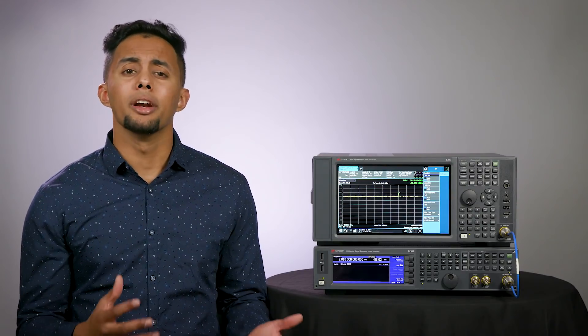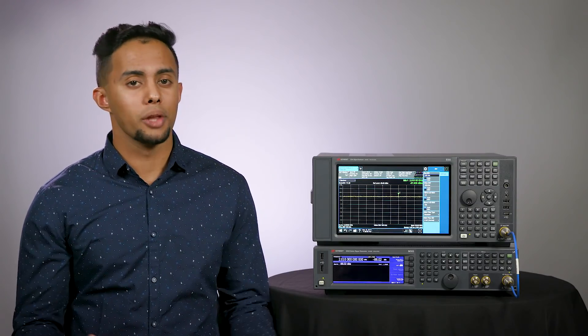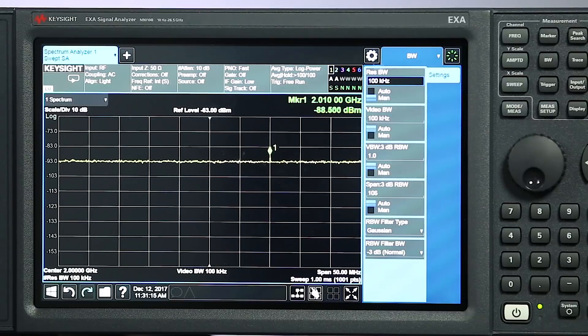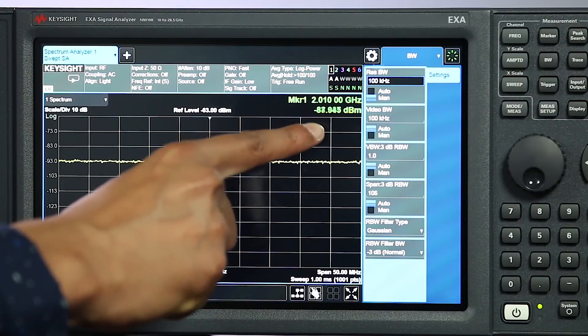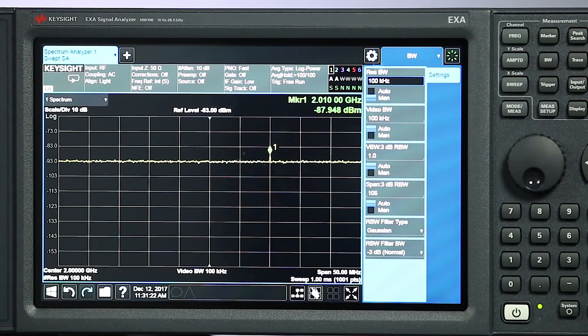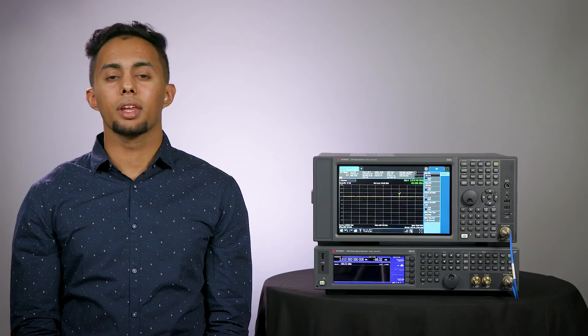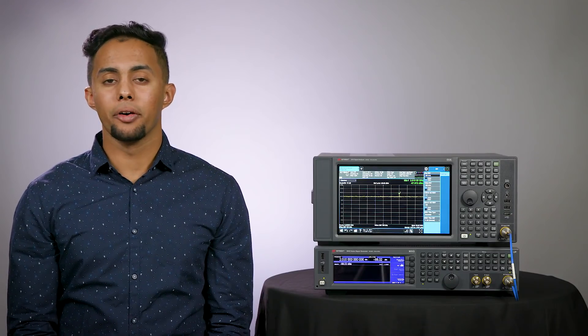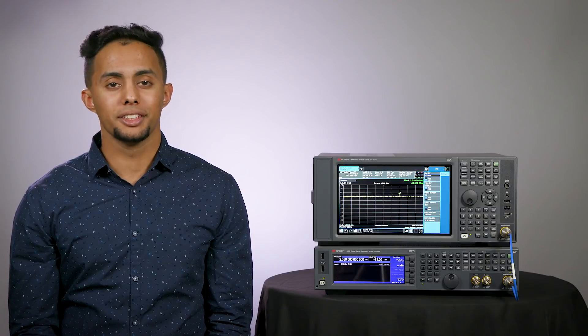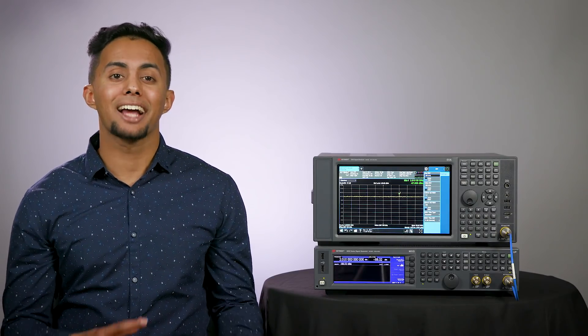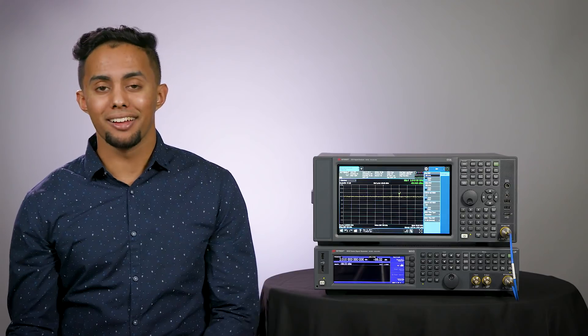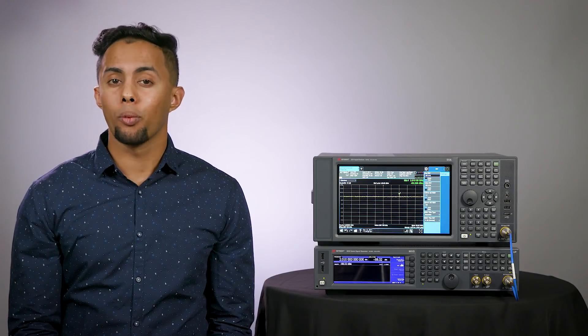Let's take a look. Let's assume we're looking for a low-level signal such as a low-level spur. On this screen we have an apparent minus 88 dBm signal at a frequency of 2.01 gigahertz, and we are sweeping with a resolution bandwidth of 100 kilohertz. We just barely see the spur here rising a bit above the noise floor, which is minus 88 dBm. An analyzer's self-generating noise limits its ability to measure low-level signals. In fact, a CW signal at the exact level as the noise floor of the analyzer results in plus 2.1 dB in error.